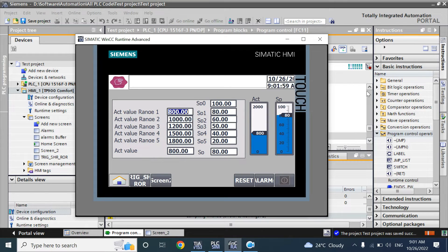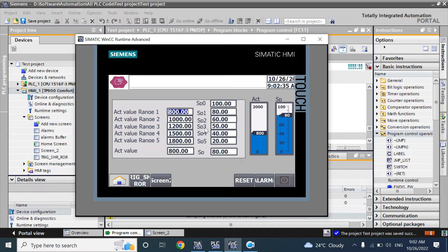Whatever range you set, we will control the speed by the setpoint. If the actual value is less than Range 1, it will take SP0. If the actual value is between Range 1 and Range 2, it will take SP1. If between Range 2 and Range 3, it takes SP2. If between Range 3 and Range 4, it takes SP3. I will show bar graphs of the actual value and the actual setpoint.